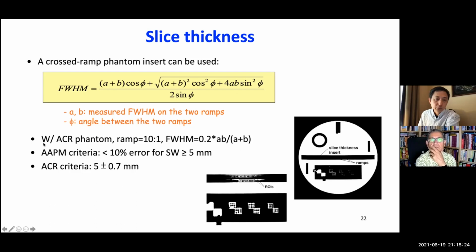And with the ACR phantom, the ramp ratio is 10 to 1. So if we plug that into the equation, it simplifies to this. A and B are the lengths of the measurement. And then using this equation, we can calculate the measured thickness. The AAPM criterion is less than 10%. The ACR criterion is 5 plus or minus 0.7 millimeter. Remember, the ACR protocol uses 5 millimeter slices. So if it's between 4.3 and 5.7, those are good.